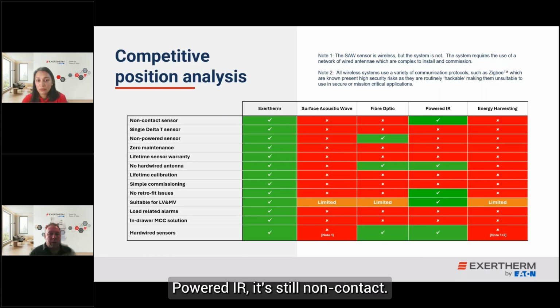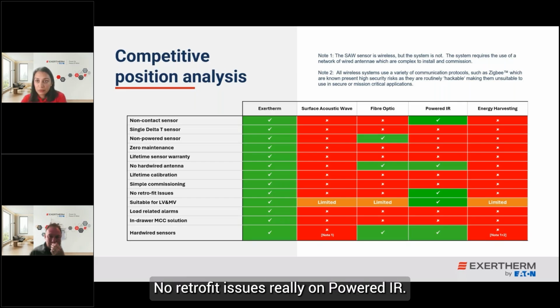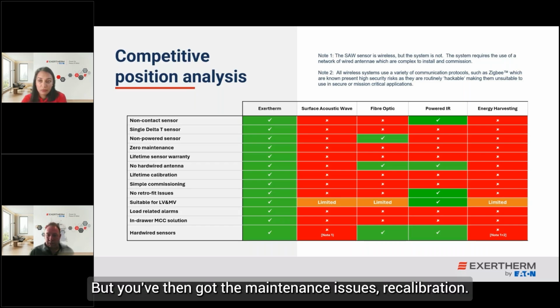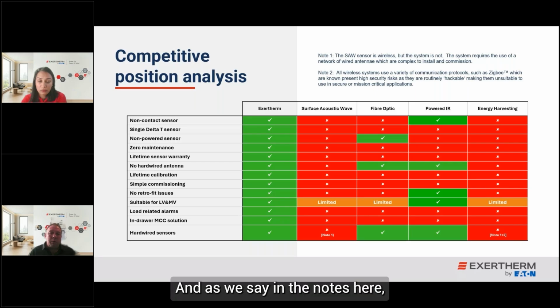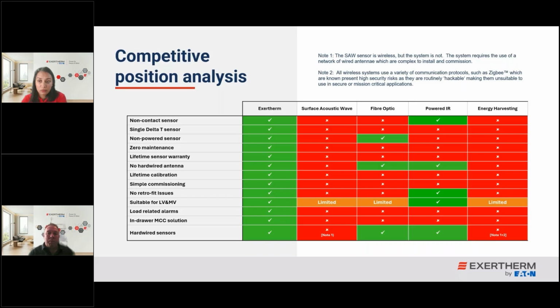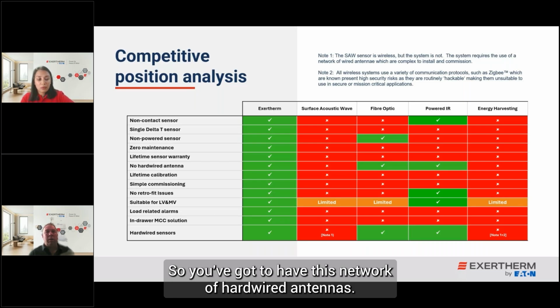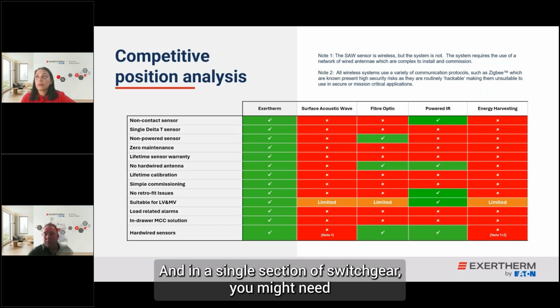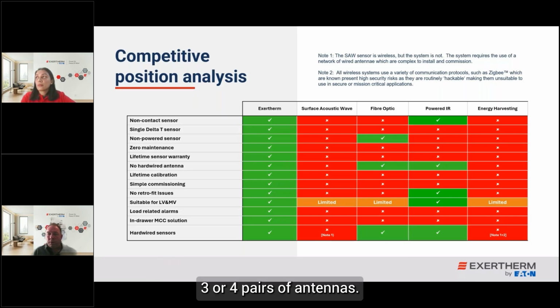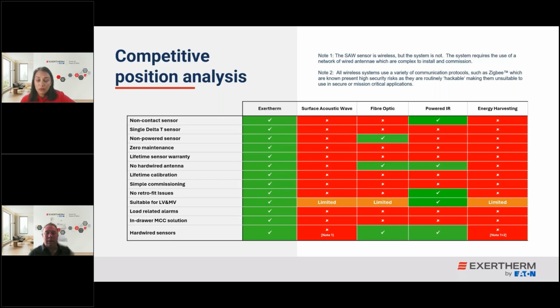Yes, some have got a green tick. Powered IR is still non-contact. Fiber optic, yeah, it's non-powered. It doesn't need antennas, neither does a powered IR. No retrofit issues really on powered IR, but you've then got the maintenance issues, recalibration. And as we say in the notes at the top, although the sensor's wireless, the system itself isn't - you've got to have this network of hardwired antennas, and in a single section of switchgear you might need 3 or 4 pairs of antennas, that's 6 to 8 antennas physically within that piece of gear just to collect all those signals, because of all the compartmentalization, the steel work, and the setup of the system.